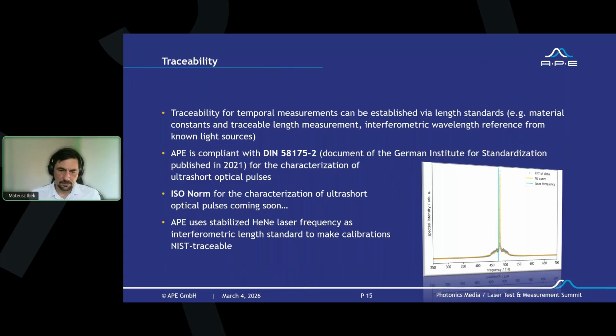And for our devices, we use, for example, stabilized helium-neon lasers, or helium-neon laser frequency as an interferometric length standard to make calibrations. NIST traceable. NIST is the National Institute of Standards in the US. On the right side, you can see the laser frequency in blue, the helium-neon laser, and the interferometer scan of this frequency Fourier transformed into frequency. And these two curves deviate a little bit. So by calibration, we match these two curves, and then we know that our delay systems that measure the pulse duration are absolutely precise to less than 1% uncertainty.